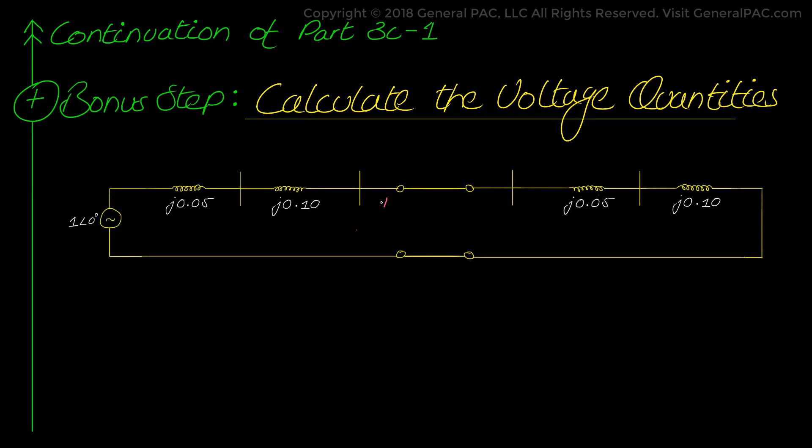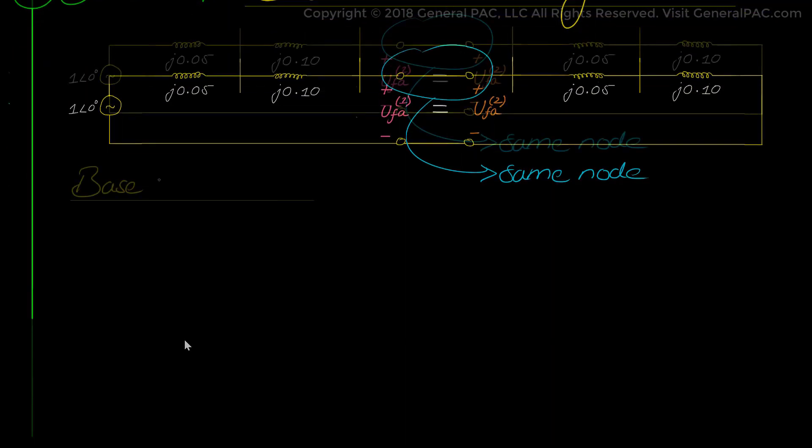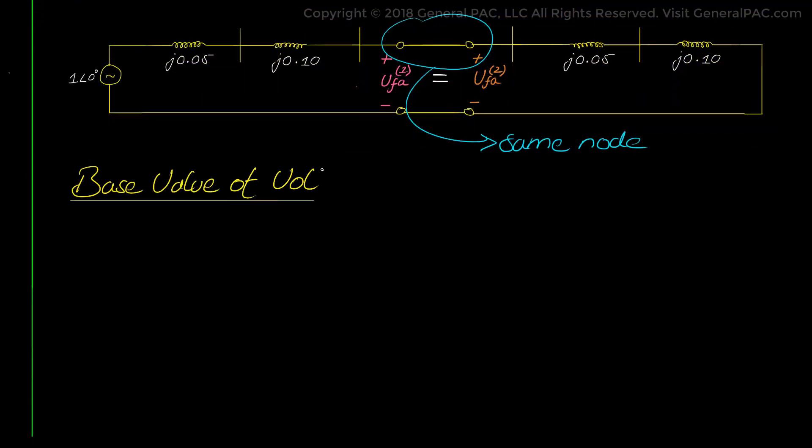We see that from the fault sequence network, the positive and negative sequence voltages at the point of the fault will be equal to each other, because we are measuring at the same node. So positive sequence voltage and negative sequence voltage will be equal, as shown in the sequence network diagram. We use the same base value as before, where VBase equals 13.8 kV divided by √3.